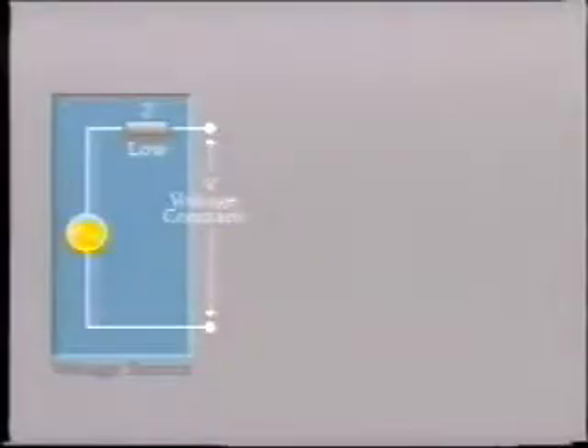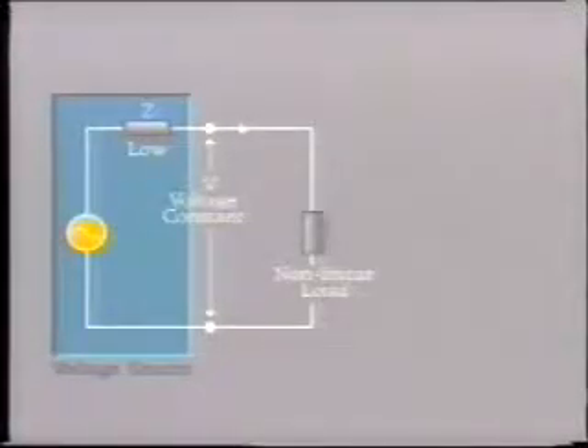Current relays should always be tested with a controlled current source, since the relay's impedance may change with current level. In fact, if we were to drive a non-linear relay from a voltage source, the current drawn would not be sinusoidal. However, with the current source, the high impedance of the source makes up most of the impedance in the complete circuit. This means changes in relay impedance will have little effect on the total circuit impedance, and thus for all practical purposes the current will be sinusoidal.